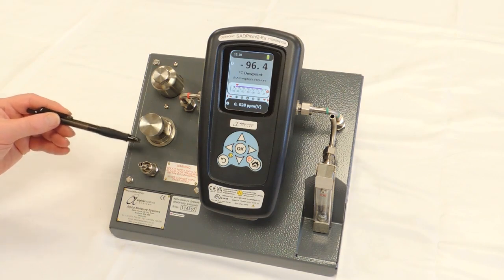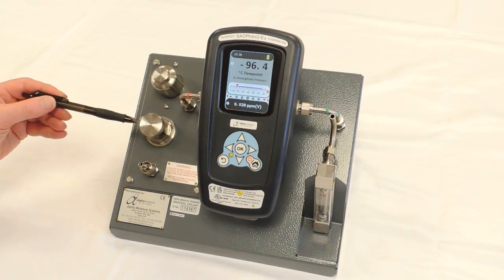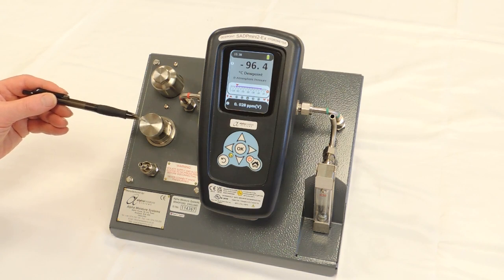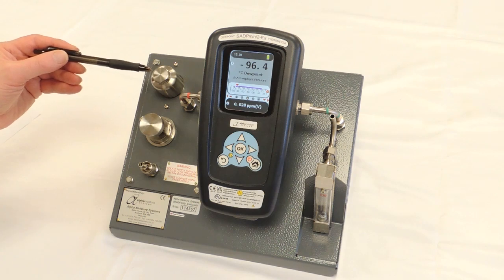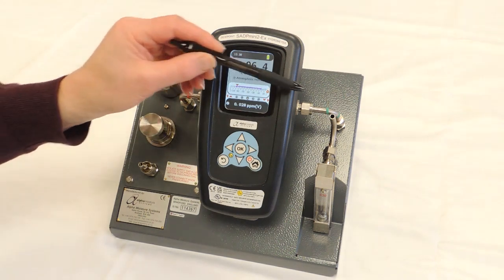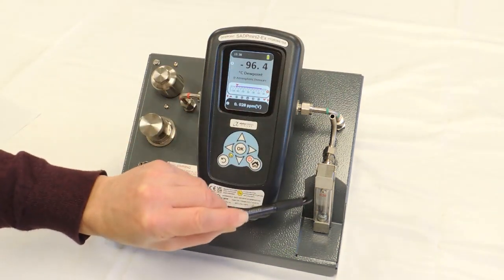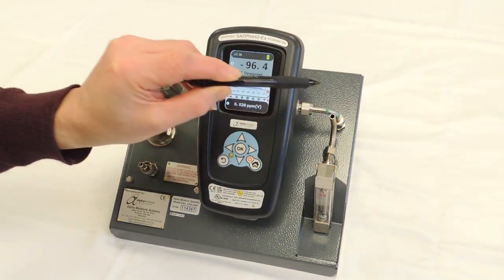From the quick connect, we go to an inlet pressure regulator which allows the pressure to be regulated down to the required pressure for the SADP Mini 2 which is less than 0.3 of a bar G. Then there's a particle filter. Then we go through the instrument, out the instrument, through a flow indicator and then out the exit pipe.